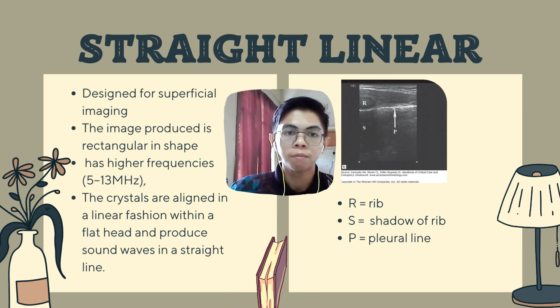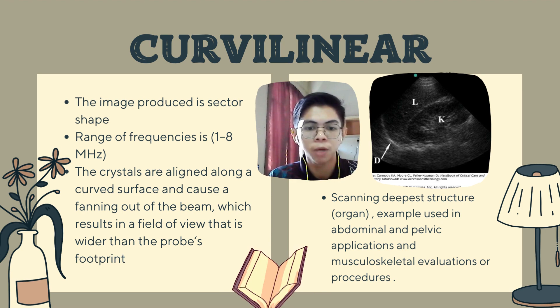The curvilinear array probe will produce an image in sector shape. This probe has a frequency range between 1 to 8 MHz. The crystals are aligned along a curved surface and cause a fanning out of the beam, which results in a field of view that is wider than the probe footprint. This probe is usually used in scanning deeper structures, which are organs. Examples of its use are in abdominal and pelvic applications and musculoskeletal evaluation or procedures in obese patients.